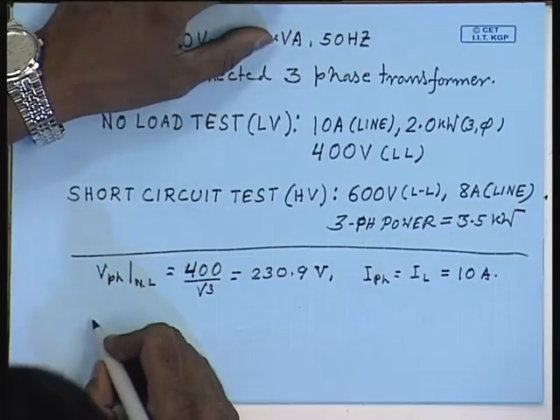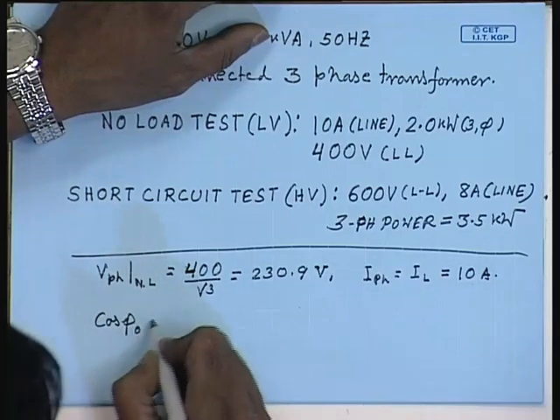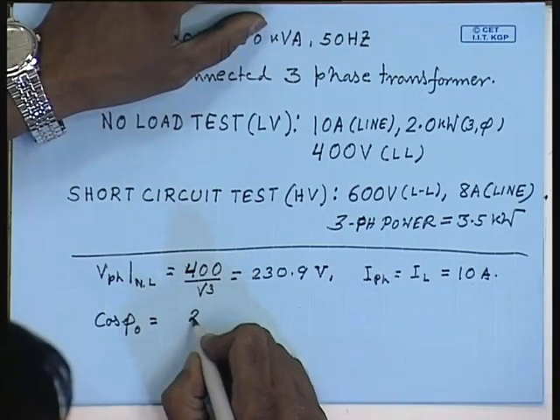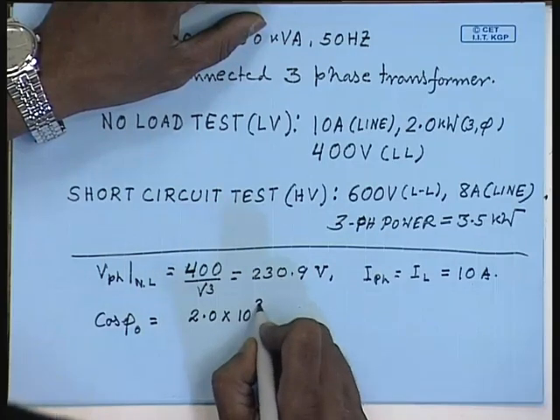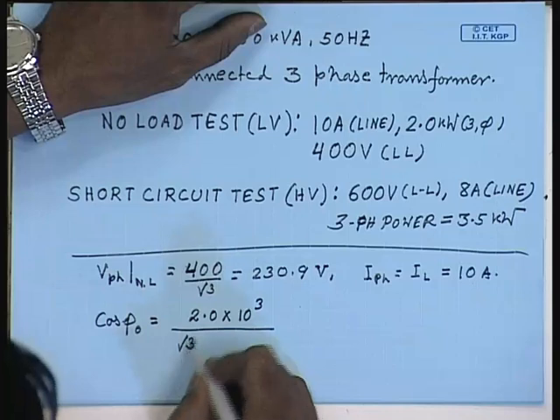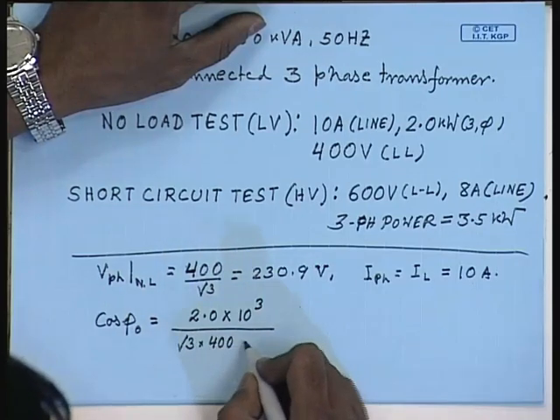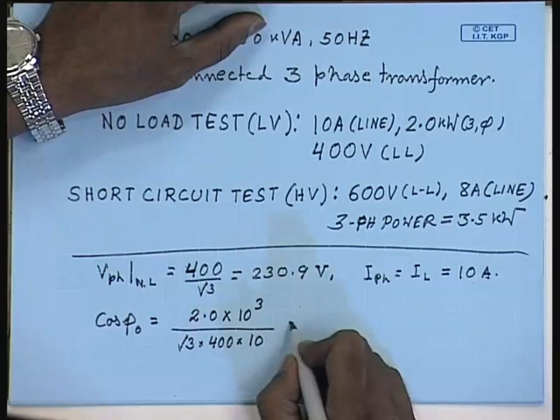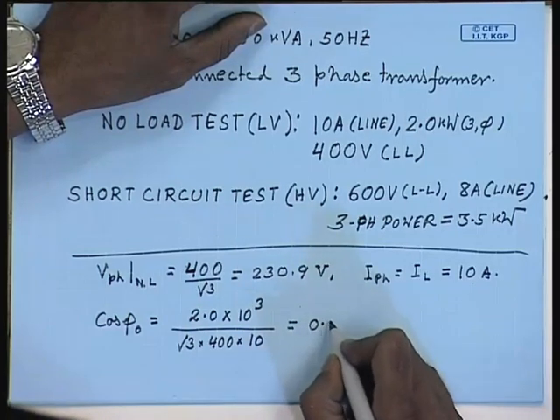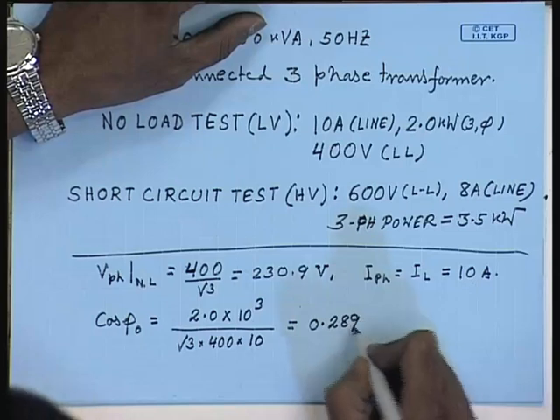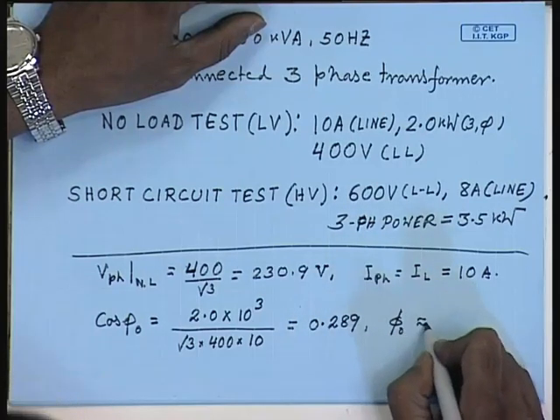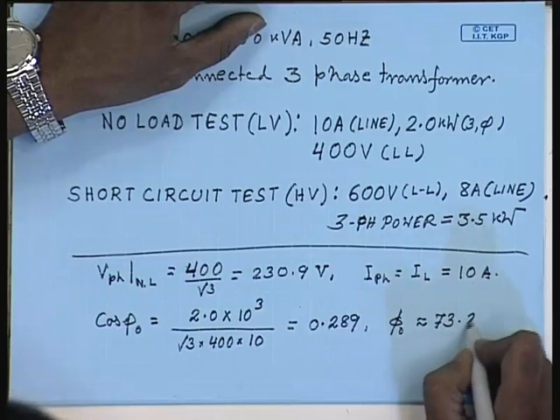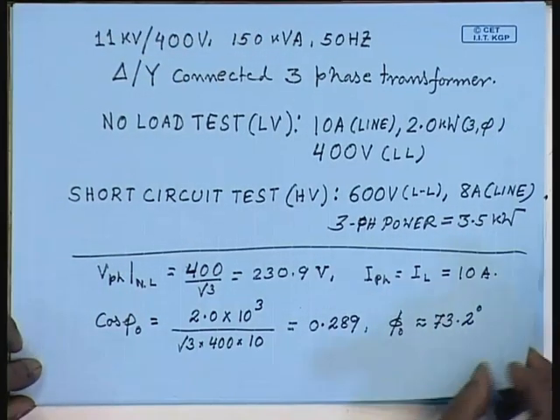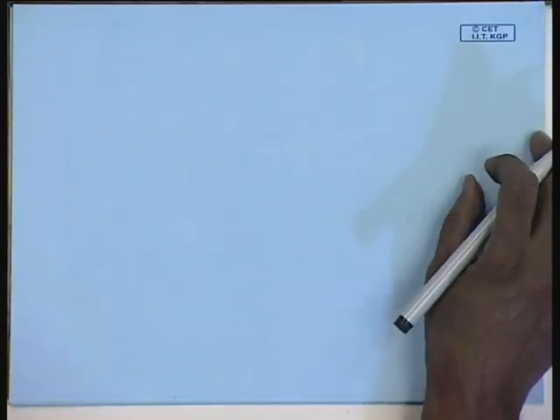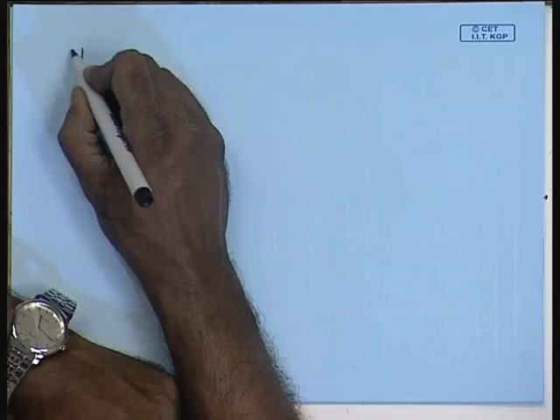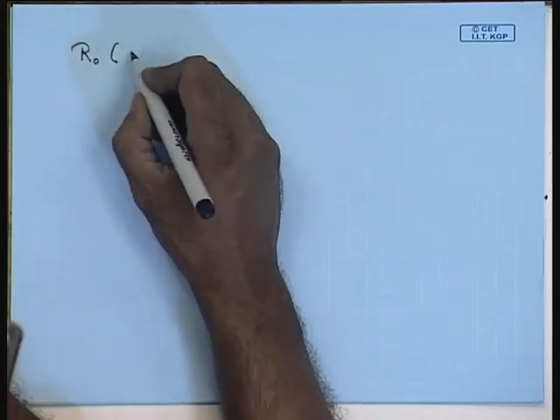The no load power factor cos phi 0 is given by no load power, 3 phase power, divided by root 3 into no load line voltage into line current, comes to be 0.289. Therefore, phi 0 comes to be approximately equal to 73.2 degrees. With this, let us find out R 0. So, this will be referred to LV side.